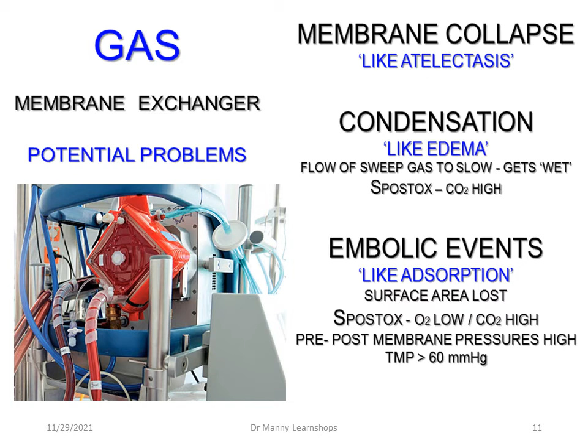So the saturation post-oxygenator is high in CO2. There's been inefficient gas exchange. Then you've got embolic events like adsorption. And this is basically where things get stuck, adsorbed onto the filter or the diffuser or the exchangers, and as a consequence of that, surface area is lost. And what happens is the saturation post-oxygenator demonstrates low oxygen, high CO2. It hasn't been efficient. So pre and post membrane pressures are typically high, and the transmembrane pressure, which you'll be monitoring, if it's your responsibility, will be greater than 60 millimeters of mercury.